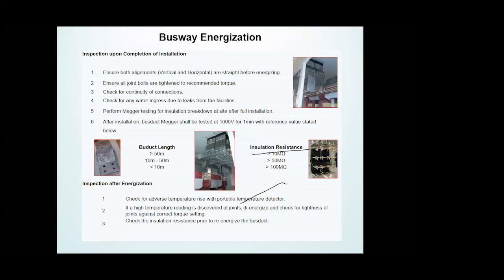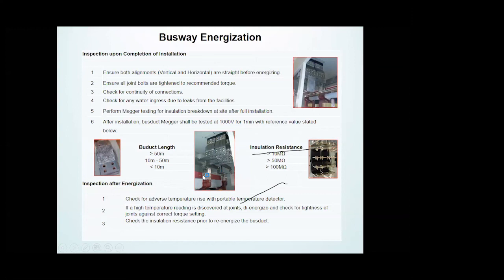After you have completed the installation, you also need to do an inspection on the busway system. One vital point is the insulation resistance value against bus duct length. After installation, the bus duct megger shall be tested at 1,000 volts for one minute with the reference insulation resistance values: if the bus duct length is more than 50 meters, insulation resistance should be more than 10 mega ohms; if less than 10 meters, insulation resistance should be more than 100 mega ohms. There is also a picture of a bus duct connected to a transformer with a flexible conductor.